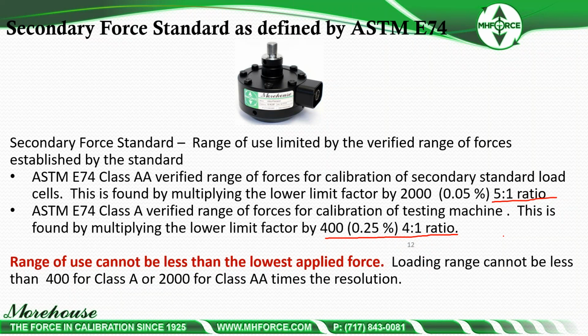You get a lower limit force factor, and you multiply that lower limit by 400 at that specific point, that first point in the Class A verified range of forces. Your TAR is exactly 4-to-1, and the range of use of all these cannot be less than the lowest applied force. This is not a zero force. This is the lowest actual applied force.